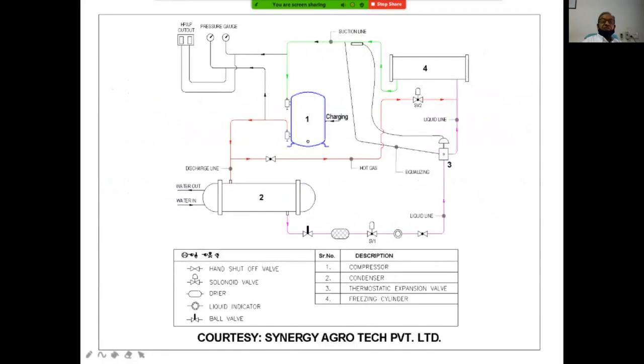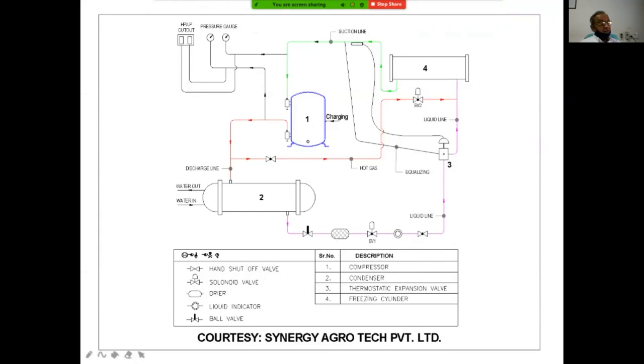If somebody is interested to see the refrigerant system, it is a simple vapor compression system. It is nothing new in that. The system is the same. This is a compressor. From the compressor, gas goes to the condenser. From the condenser, it goes through a valve, then filter, solenoid valve, liquid indicator, again a valve, the expansion valve, and into the freezing cylinder, and the liquid is evaporated and taken back to the compressor. And one connection is given for hot gas from the condenser to the freezing cylinder. In case the ice cream is too frozen and not coming out or is jammed, we can supply the hot gas, and by hot gas we can heat the ice cream and take it out. That is a simple refrigeration system, my dear friends.